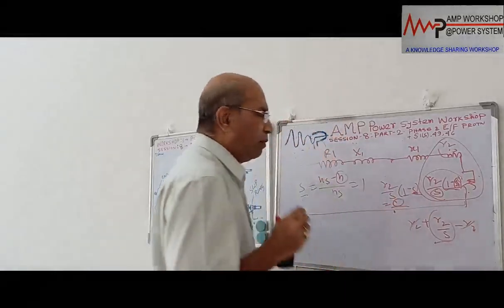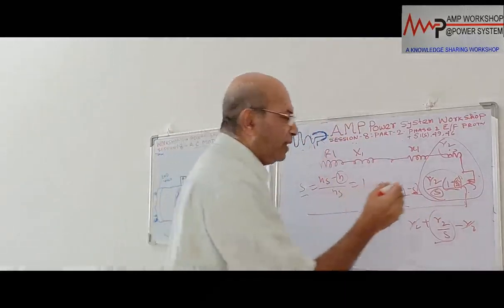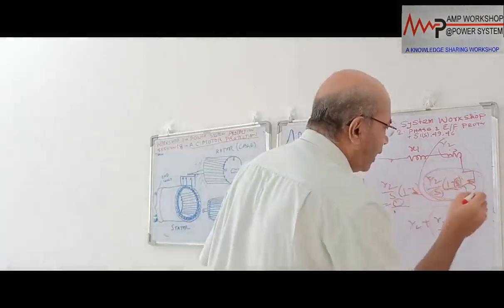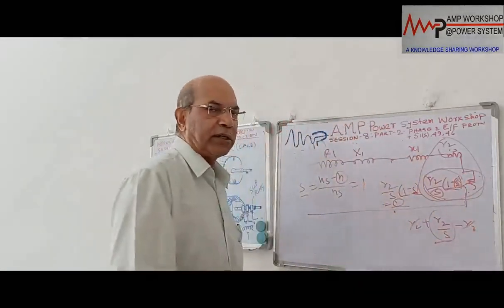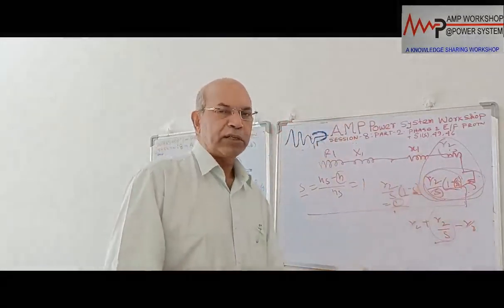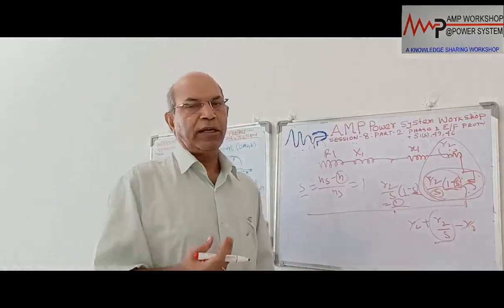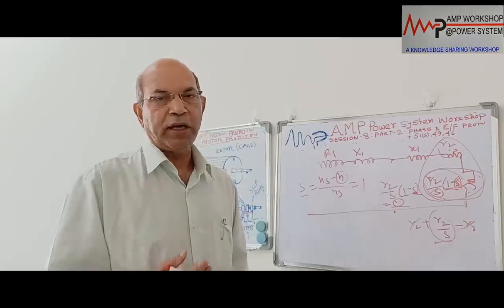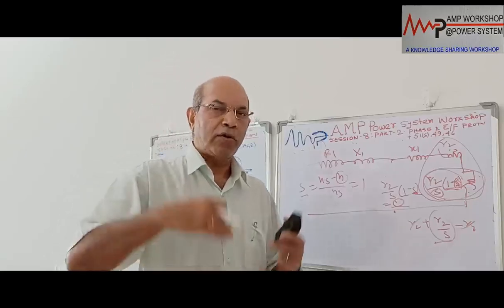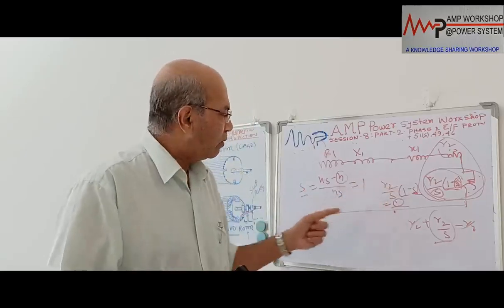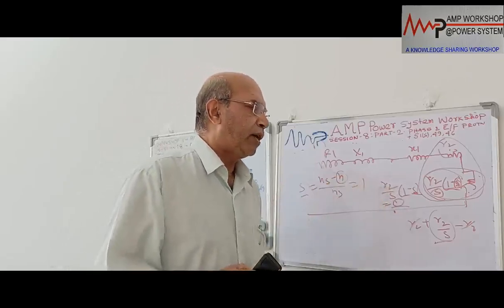That means during start of the motor, this mechanical load equivalent resistance transferred to the rotor side becomes 0. That means the motor is getting started at the short circuit condition. So we know when the short circuit condition exists, the current will automatically be very high. That is the reason why the motor current is higher during starting time.